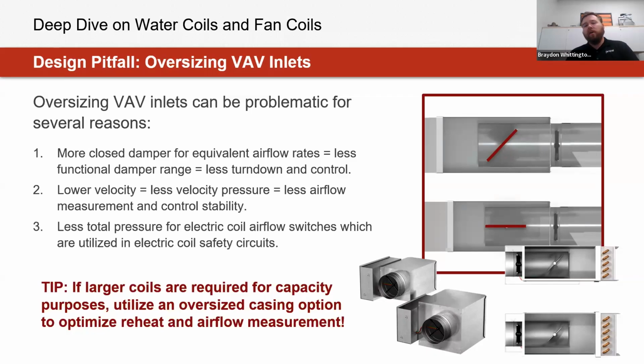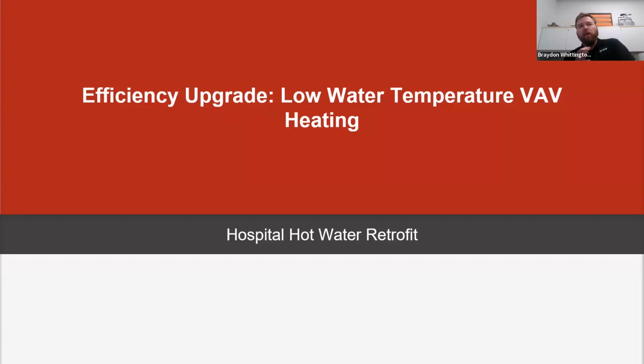A typical rule of thumb for everyone on the call: when dealing with conventional boiler systems, around 180 for terminal water reheat is typically most effective with a one-row coil. Condensing boilers, around the 160, 140 mark, is when we start to look at two-row coils, or maybe these oversized casing or high capacity options. And as we get lower into the heat pump range of around 120, that's when you start looking at bumping up the number of rows, or playing around with the circuitry of the coil to handle these lower temperatures, or maybe more custom coil solutions.